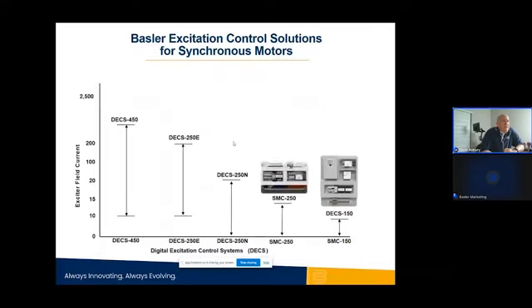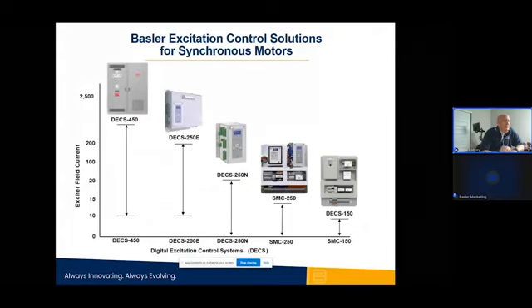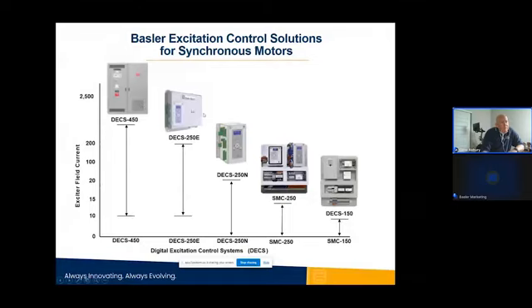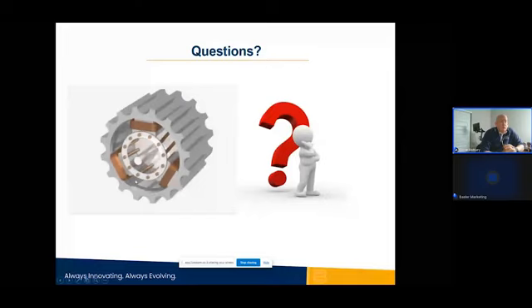And then the Basler excitation control solution for synchronous motors with the 250. Probably the most popular types are the DECS 250E for slip ring motors and the DEX SMC 250 for brushless excited motors. Those would be the two. We have used 450s and their predecessors, the 400s, on many applications that require more than 200 amps. And then the DECS 150 is ideal for certain motor applications. You don't get all the features and functionality, but for small brushless excited motors, it might be ideal. So with that said, I went a little bit over, but are there any questions?